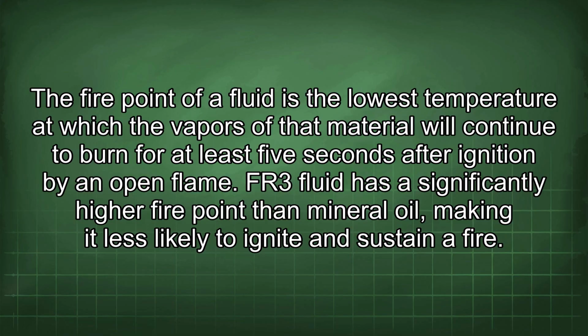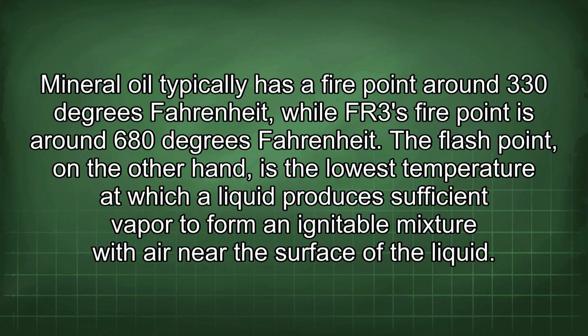FR3 fluid has a significantly higher fire point than mineral oil, making it less likely to ignite and sustain a fire. Mineral oil typically has a fire point around 330 degrees Fahrenheit, while FR3's fire point is around 680 degrees Fahrenheit. The flash point, on the other hand, is the lowest temperature at which a liquid produces sufficient vapor to form an ignitable mixture with air near the surface of the liquid.